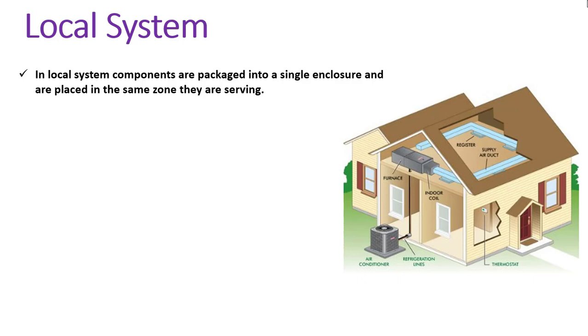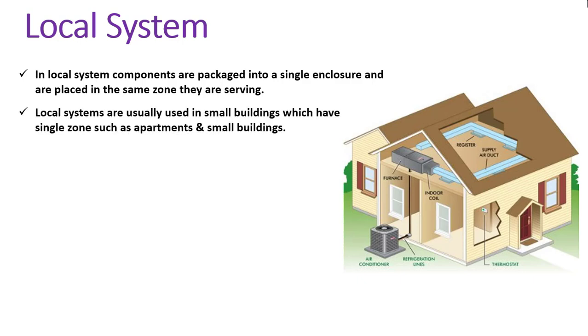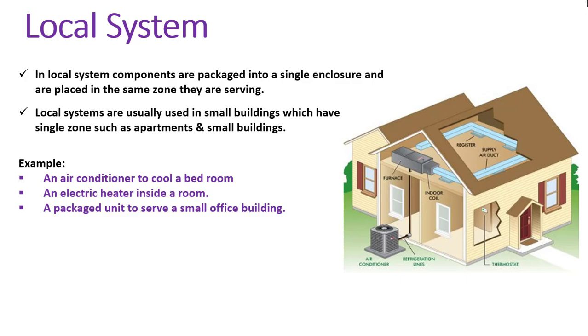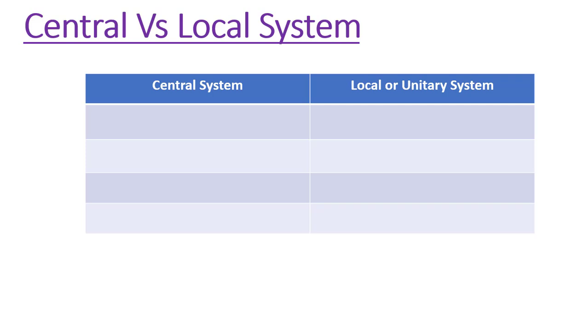In a local system, components are packaged into a single enclosure and placed in the same zone they are serving. Local systems are usually used in small buildings with single zones, such as apartments and offices. Examples of local systems include an air conditioner to cool a bedroom, an electric heater inside a room, or a package unit to serve a small office building.